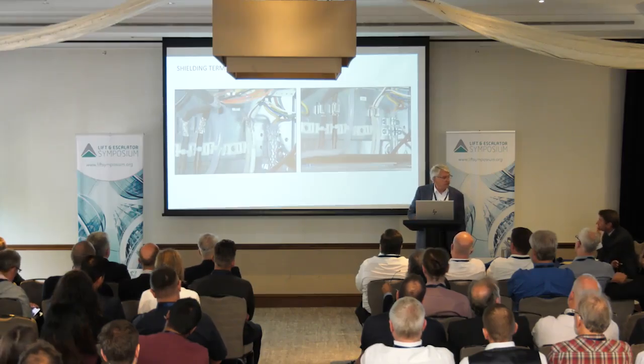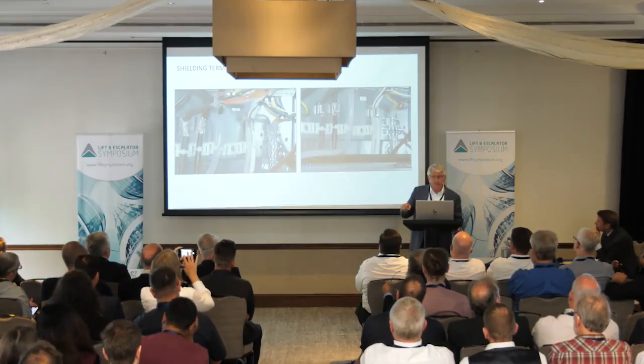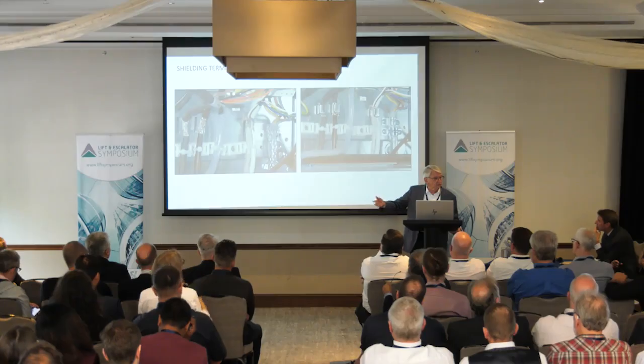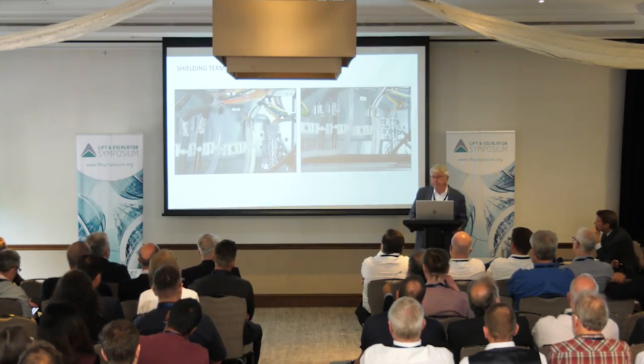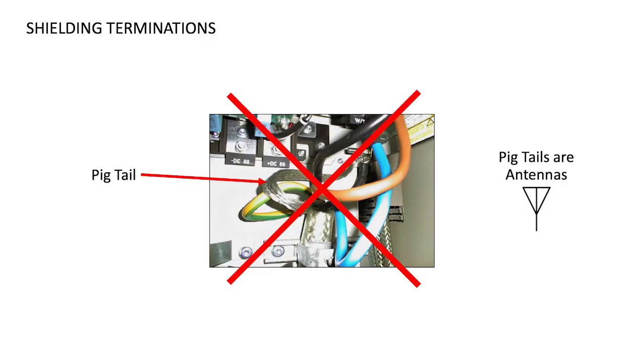the shielding. And what that does is it takes advantage of the skin effect, and it gives you the most direct path to the earth or grounded controller frames. This is the right way to do it. Not always done. In fact, more often than not, from what I found, it wasn't done.